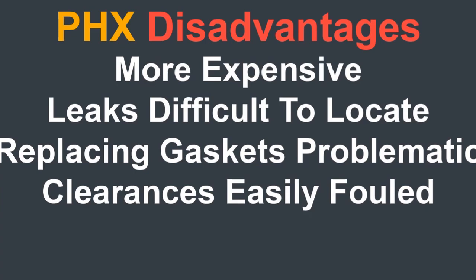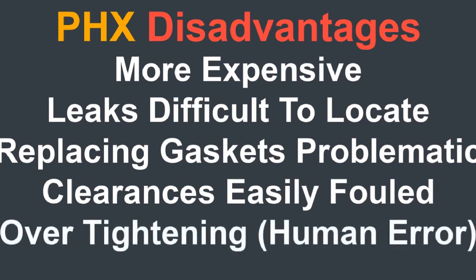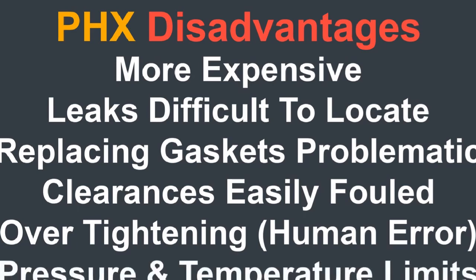When reassembling the plate stack, over-tightening the clamping bolts can lead to crushing of the plates, which will damage the plate corrugations and squeeze out the gaskets. If the gaskets are squeezed out, the plates will no longer seal correctly. Plate heat exchangers are not suitable for high pressure applications because the gaskets would be expelled by the system pressure. This situation is referred to as gasket blowout. However, it is possible to get around this problem by using a gasketless design. These designs usually use brazed or welded plates. Brazed and welded plate heat exchangers are more suitable for higher temperature and higher pressure applications.